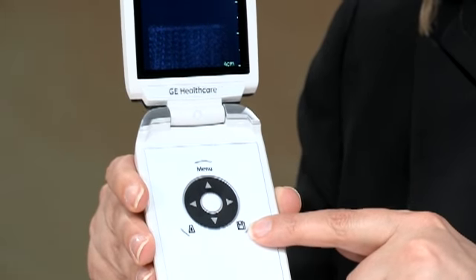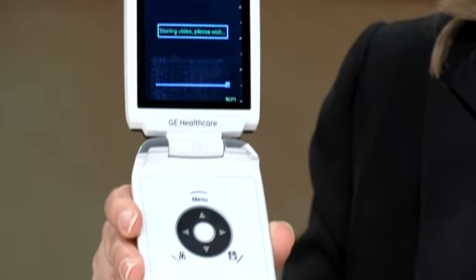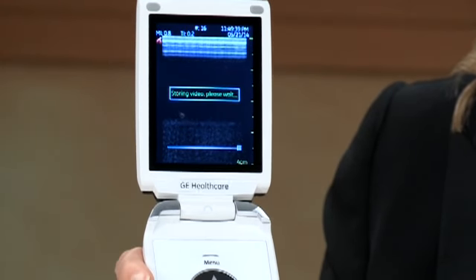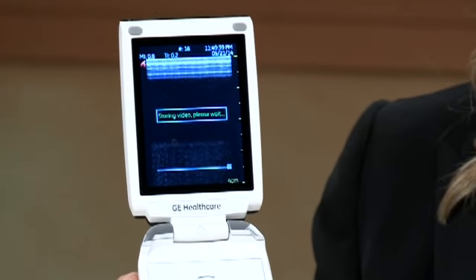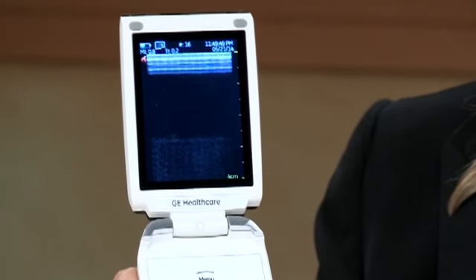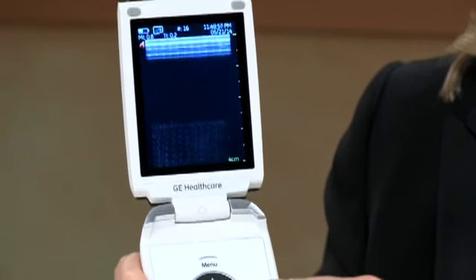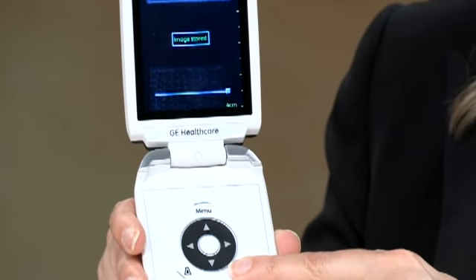Let's walk through how to store clinical information on the Vscan device, as well as how to access it in the image gallery. When live scanning, the user has the ability to store loops, still frames, as well as a voice recording. Here, the linear transducer is active. If I press the store key while live scanning, a video will be stored to the archive. For non-cardiac applications, the respective store time can be defaulted anywhere between 1, 3, and 6 seconds. Here, that cycle was stored. If I choose to freeze and then store, that single frame will be stored.